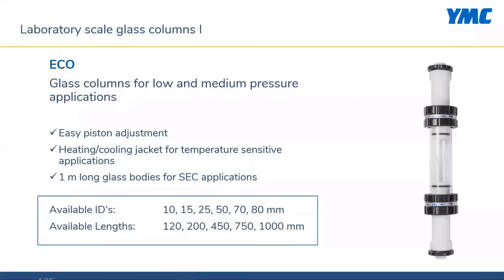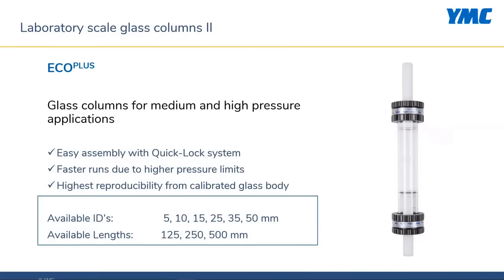We have the Eco and Eco Plus line. Eco columns are designed for low and medium pressure applications, characterized by easy piston adjustment due to the squeezed O-ring sealing principle. They are a perfect match for temperature-sensitive applications, as a heating-cooling jacket is optionally available. Eco Plus glass columns are designed for medium and high pressure LPLC applications, characterized by easy assembly with a quick lock system. Due to higher pressure limits, you can increase the flow rate and generate faster runs.